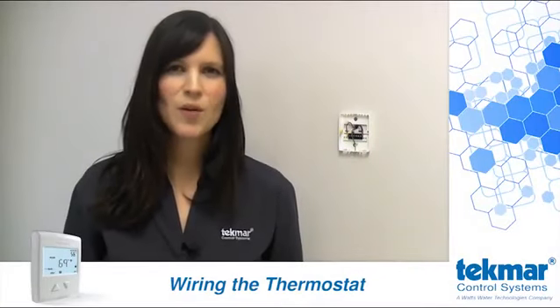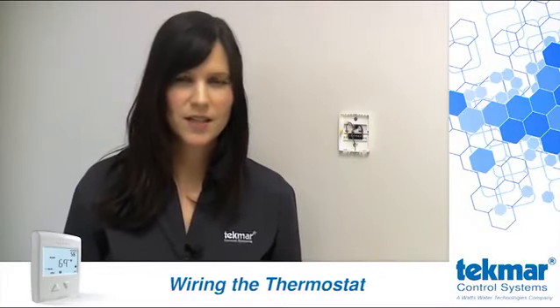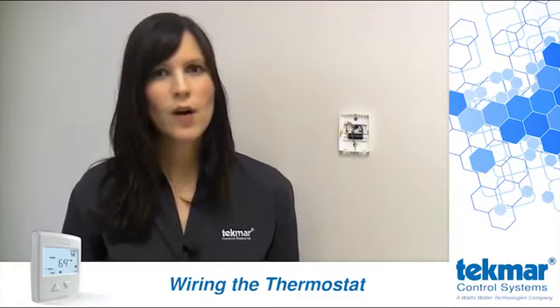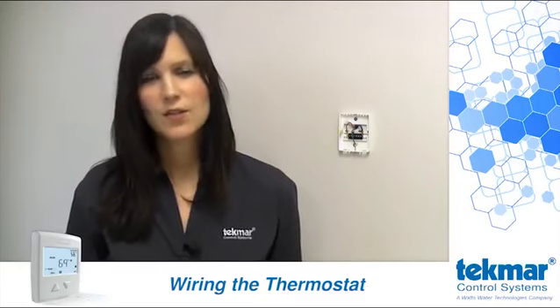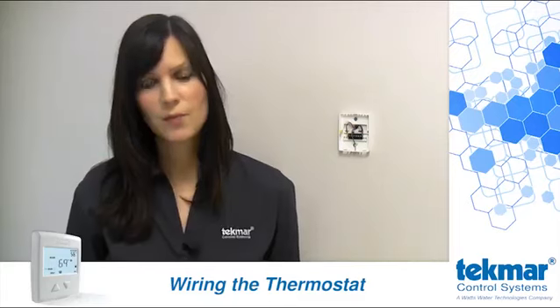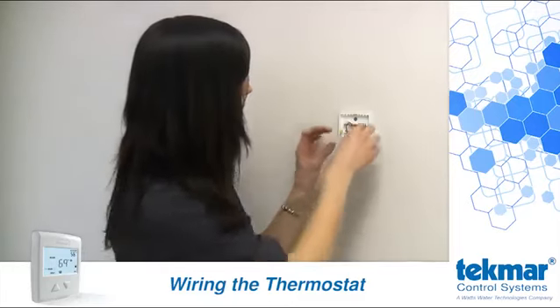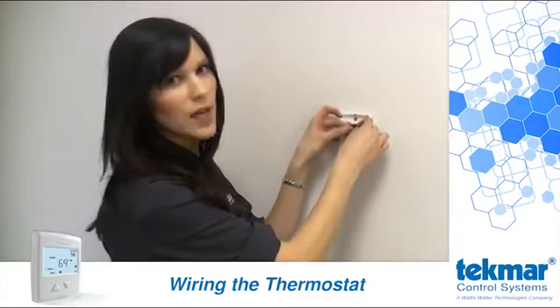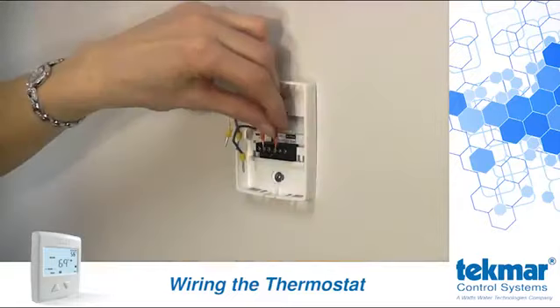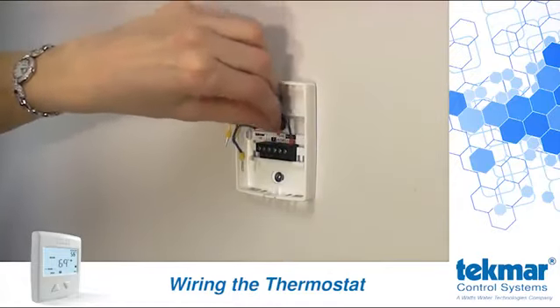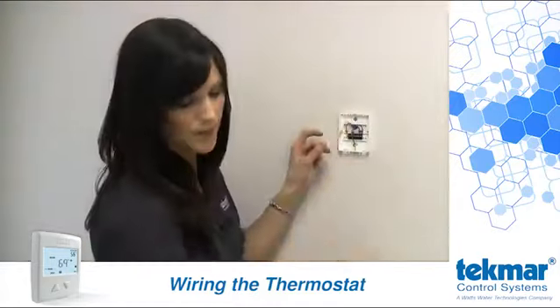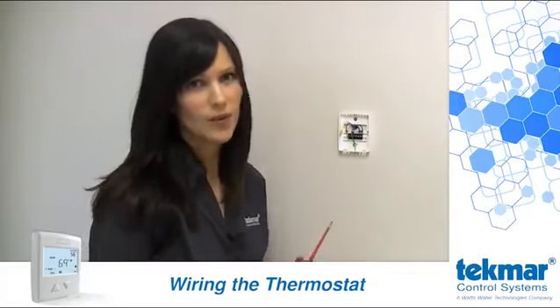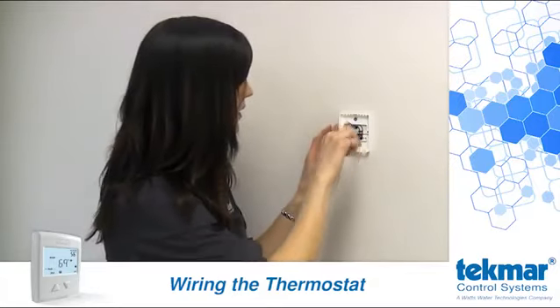As you can see, I already pulled the wire through to the thermostat. We're going to start by connecting the wires to the sensor, to the transformer, and to the heat relay. Starting with the sensor wiring, I have two wires coming from my sensor, which I am connecting to the S1 and the COM terminals on the 518. Now these connections are not polarity sensitive, so it's impossible to get it wrong.